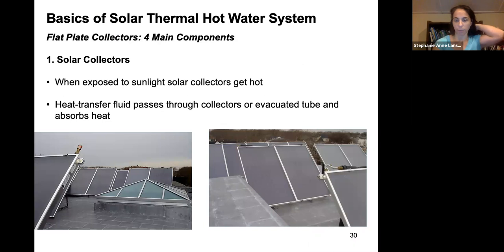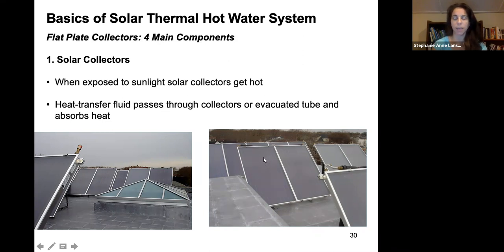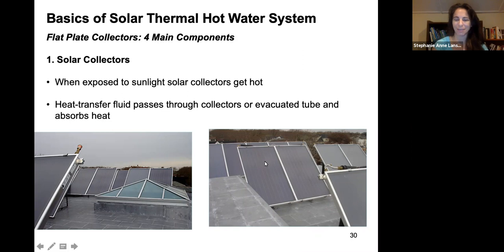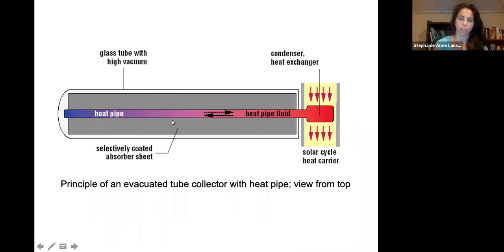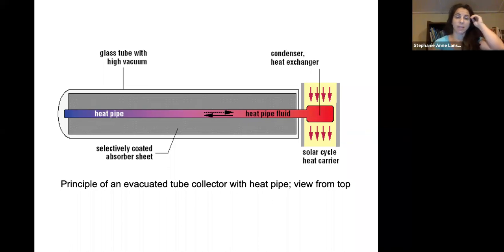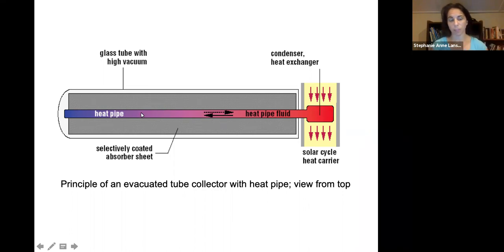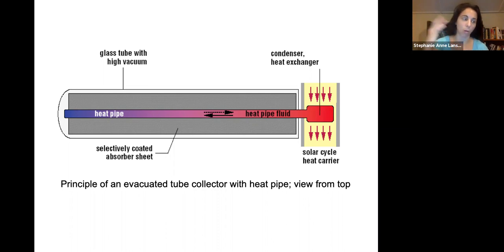With evacuated tubes, there is an evacuated glass tube and a heat condenser pipe inside that is heated. The four main components of a solar thermal system are: the collector — which gets hot when exposed to sunlight and can actually burn you — through which a heat transfer fluid passes and absorbs heat. In an evacuated tube specifically, instead of a glycol tube in the middle, there is a heat pipe inside a glass tube with a high vacuum, so no heat is lost. Once heated, the heat pipe condenses with a heat exchanger and the glycol or water carries the heat to where it will be used.